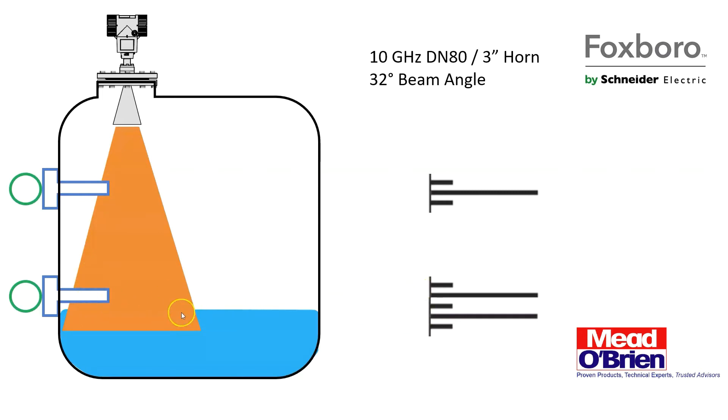What you as a user could do is tell the radar, ignore this. That's not the level. That's a thermowell. And ignore this. That's a thermowell. That's not the level. And the radar goes, okay, I'm going to ignore these two signals, reflections I get from these. And you go on your way.